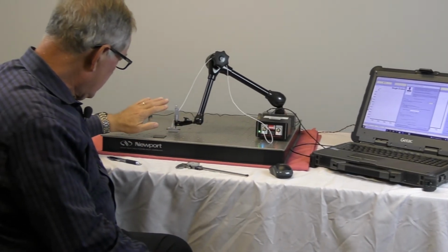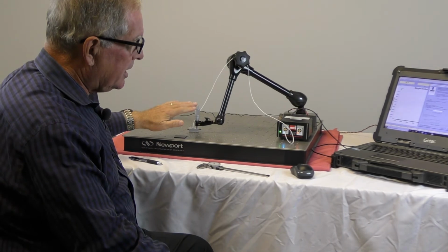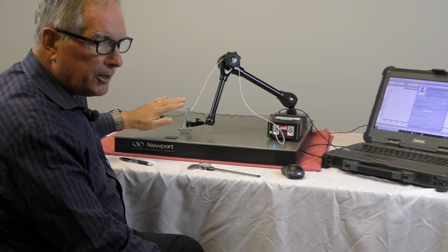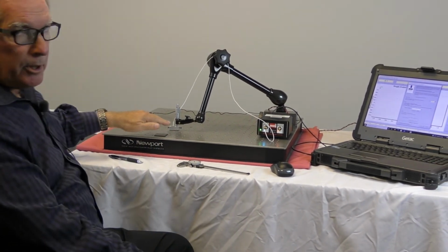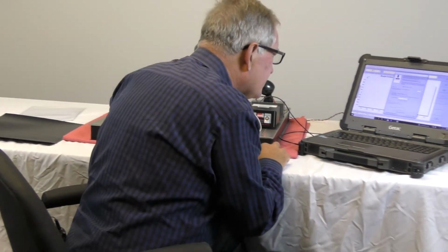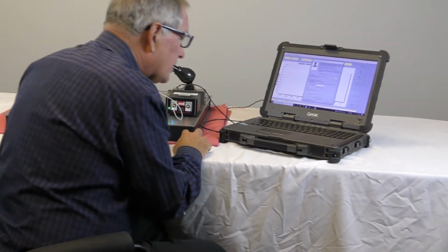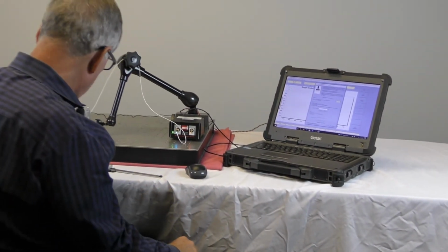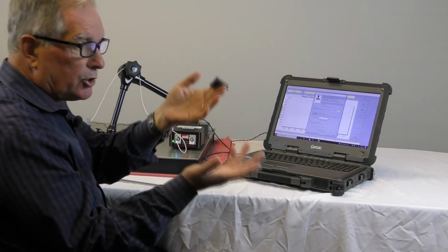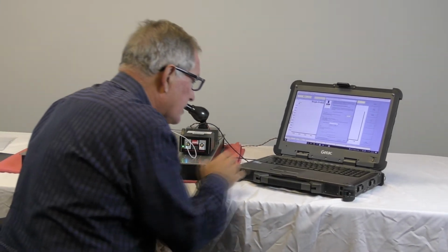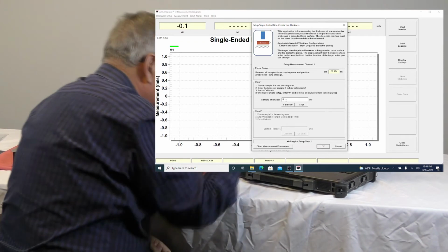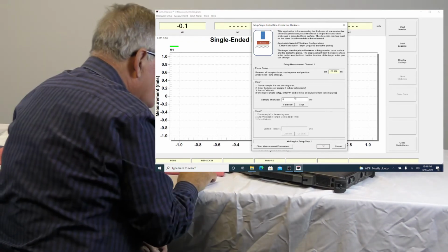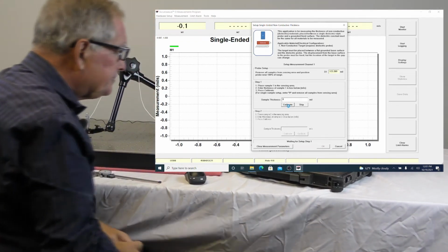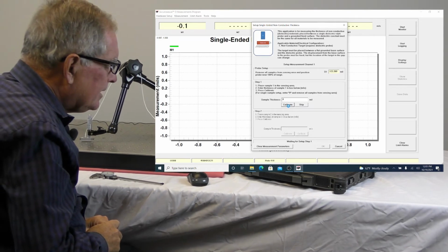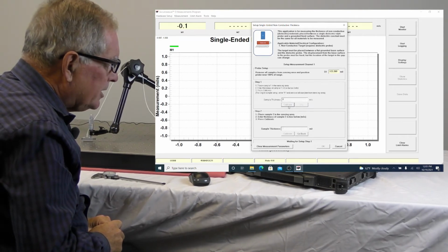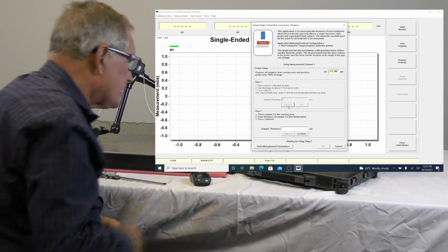Then for the next step, we want to calibrate the gap with nothing in there, okay? So it's just the probe looking at the bare metal. We could do a two-step calibration with two different types of material, but in this case, we're just going to do it with one to show you how easy it can be done. So nothing's in the gap. I'm going to enter 0 here, and I hit calibrate. It takes a few seconds for the probe to read it. It averages it a number of times, and that's entered.